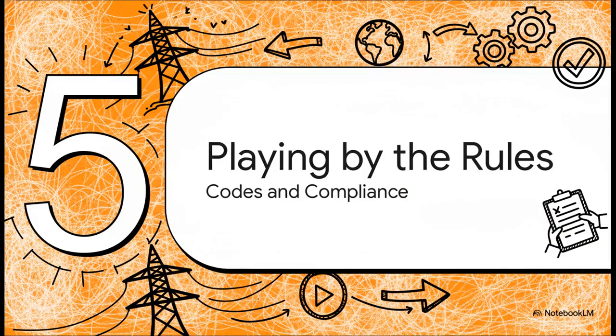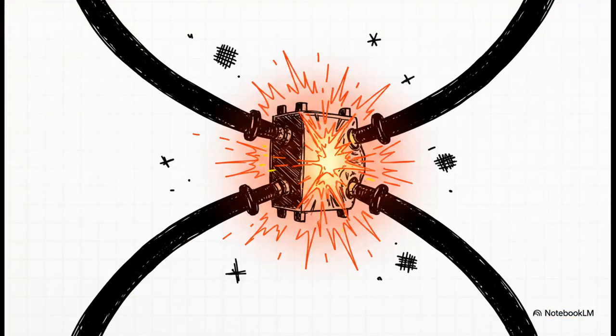Finally, let's wrap up with Section 5, Playing by the Rules, Codes and Compliance. Now, I really want to slow down here for a second to emphasize just how catastrophic a mix-up can be. Remember our math from earlier? If you try to take a smaller, lighter 60 Hz transformer and hook it up to a 50 Hz power grid without radically derating the voltage, the lower frequency instantly increases the magnetic flux way beyond what that smaller iron core can handle. The core will magnetically saturate, it will violently overheat, and it will absolutely fail.